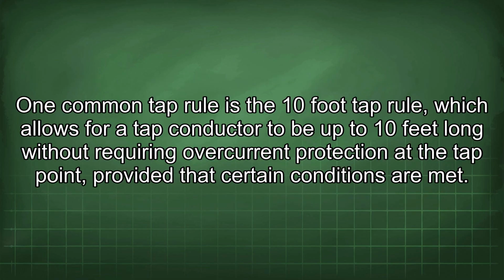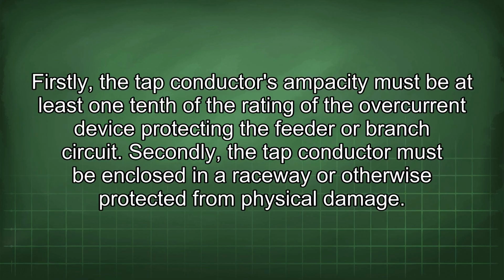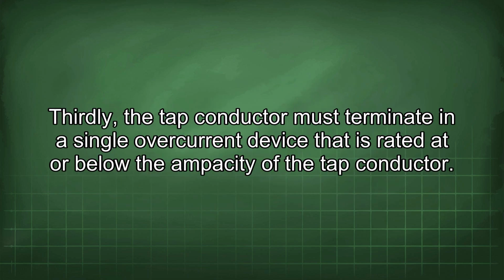One common tap rule is the 10-foot tap rule, which allows for a tap conductor to be up to 10 feet long without requiring overcurrent protection at the tap point, provided that certain conditions are met. Firstly, the tap conductor's ampacity must be at least 1/10 of the rating of the overcurrent device protecting the feeder or branch circuit. Secondly, the tap conductor must be enclosed in a raceway or otherwise protected from physical damage. Thirdly, the tap conductor must terminate in a single overcurrent device that is rated at or below the ampacity of the tap conductor.